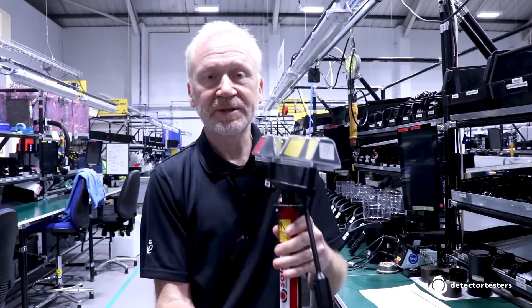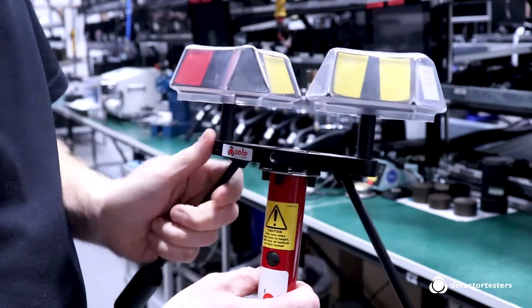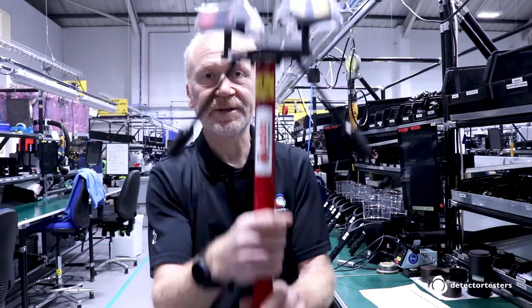When you go above 6 meters and you're working at up to 9 meters maximum height, you lock it in the lower setting and that locks the gimbal so you're coming straight underneath the detector.